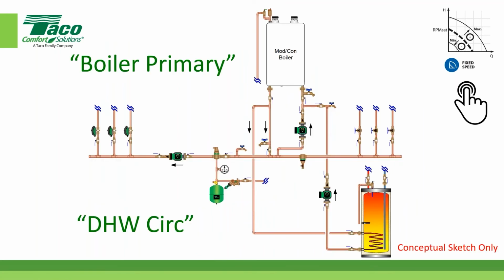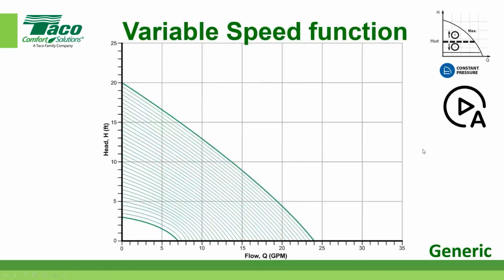So we're still in fixed speed. Notice over here, we're still in fixed speed. And we still have one pump that's not going to be in fixed speed, so we'll put a red X on that. But by all means, for the indirect and for the boiler pump, I'm going to use fixed speed. Is everybody okay with that? Again, you're going to get copies of this that'll help you remember what we're talking about.